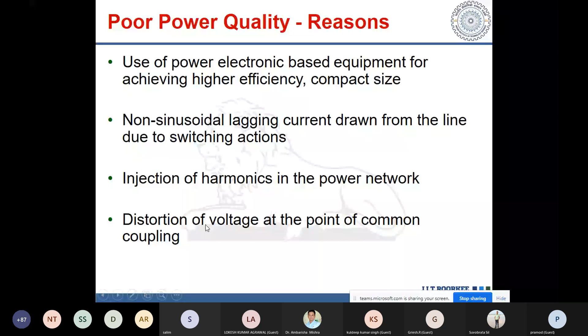As I have explained, if the voltage is non-sinusoidal, there will be excessive losses and heating in motors. If you have connected a capacitor, that capacitor may be subjected to non-sinusoidal voltage, and there is a possibility the capacitor may burst. The transformers are also subjected to non-sinusoidal voltage, so there will be increased harmonics, overheating due to non-sinusoidal current, and insulation failure due to non-sinusoidal voltage.